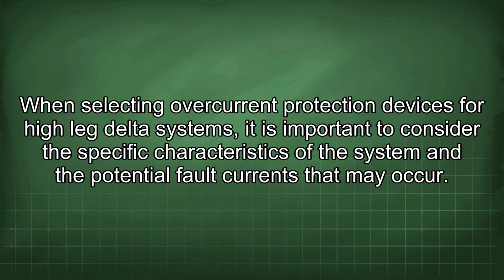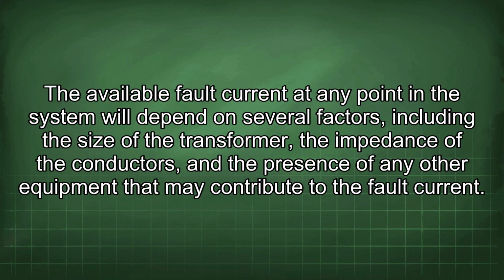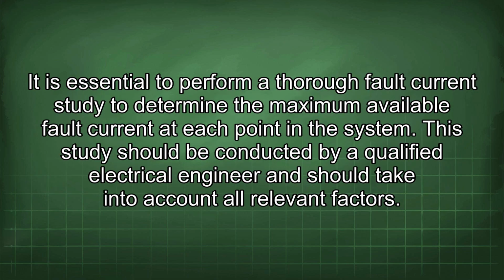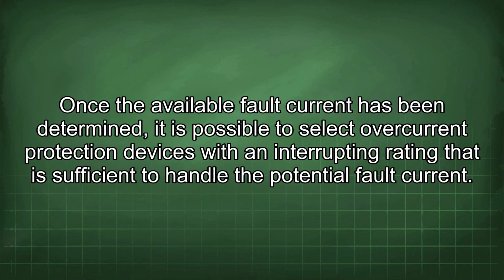When selecting overcurrent protection devices for high-leg delta systems, it is important to consider the specific characteristics of the system and the potential fault currents that may occur. The available fault current at any point in the system will depend on several factors, including the size of the transformer, the impedance of the conductors, and the presence of any other equipment that may contribute to the fault current. It is essential to perform a thorough fault current study to determine the maximum available fault current at each point in the system. This study should be conducted by a qualified electrical engineer and should take into account all relevant factors. Once the available fault current has been determined, it is possible to select overcurrent protection devices with an interrupting rating that is sufficient to handle the potential fault current.